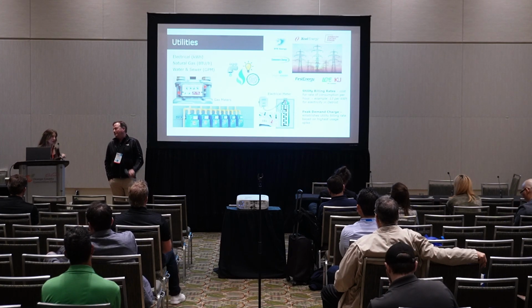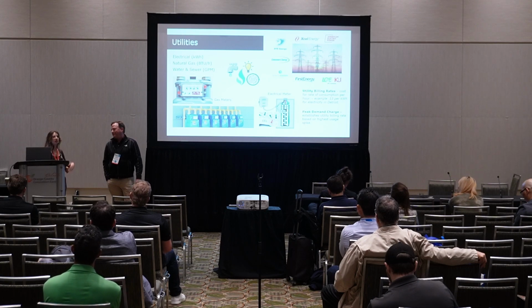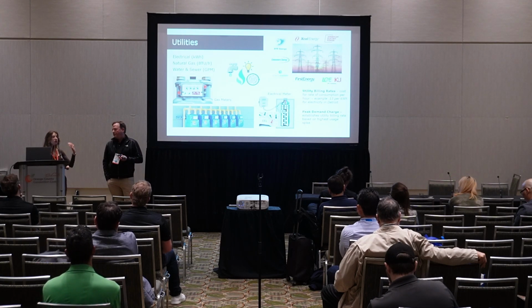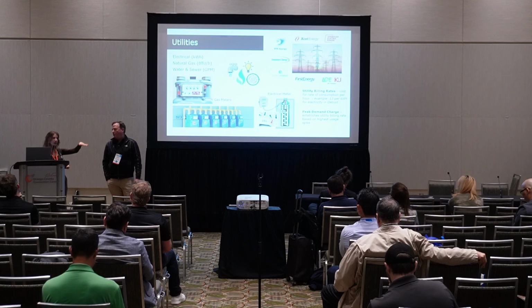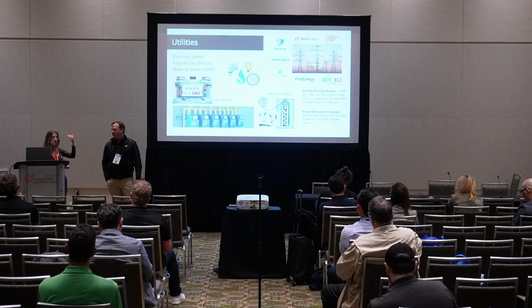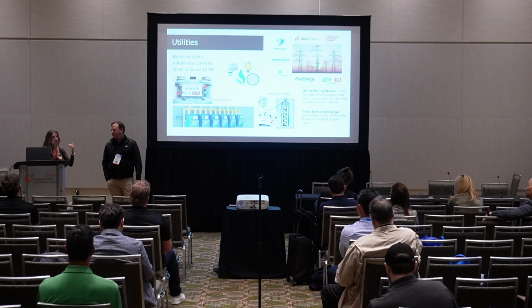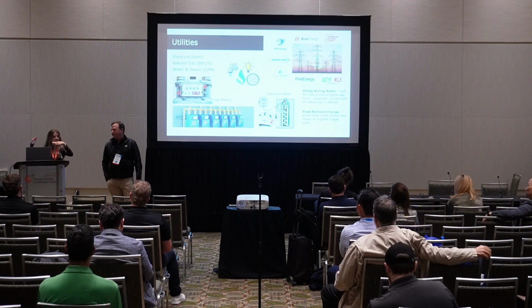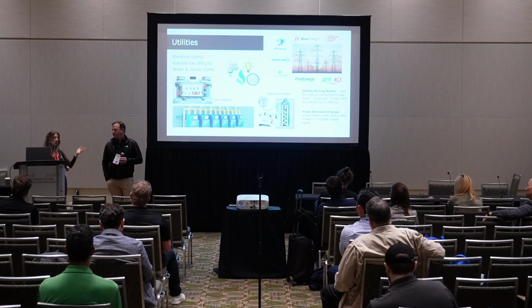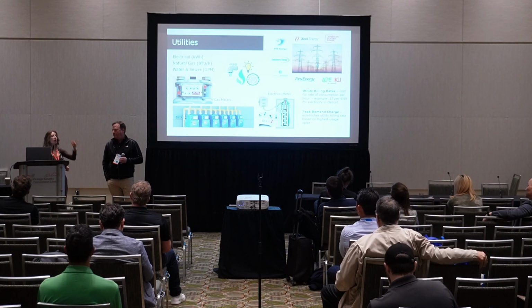One other thing, going down the load shedding rabbit hole: consider if you're load shedding because it's really hot out. You're relaxing set points, turning things down. What happens when that load shedding strategy stops? Everything peaks, and it's like you didn't reduce your peak, you just shifted it, so you're still paying the same amount, because as soon as you relax that strategy, all those rooms calling for heating or cooling this whole time now drive it all at once. You have to be careful, because the goal isn't to just shift it, but to reduce it overall.